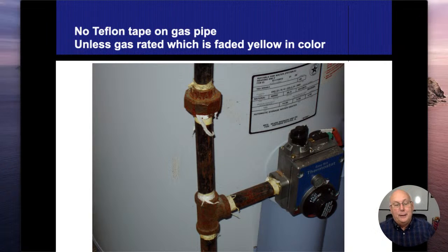Again, I'm a big fan of using gas detectors, and we would take our little Klein tool and check each and every joint to see if it's leaking. Because it's not allowed, I just don't want to take ownership of things. So these are things that I do document if I see the white tape on there. But I just can't in my right mind tell someone, undo this, put the pipe dope in, or the yellow tape in there, because it's the raw material that was used. Unless I have some sort of intimate knowledge that this has created problems, and I just don't have that.